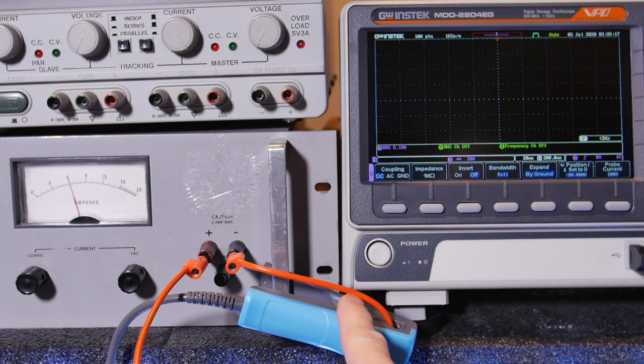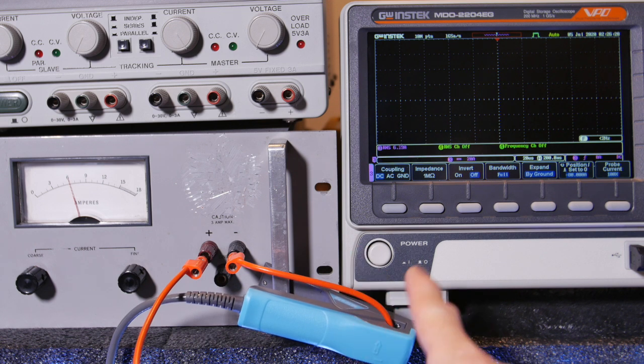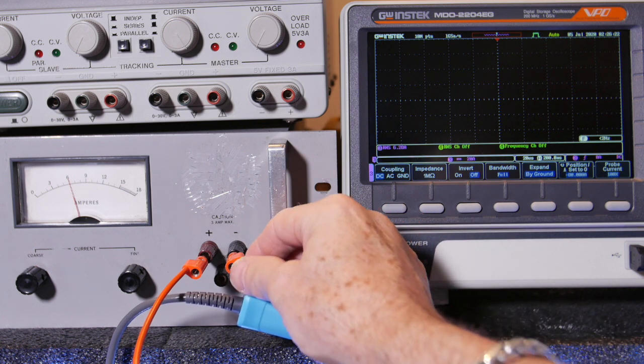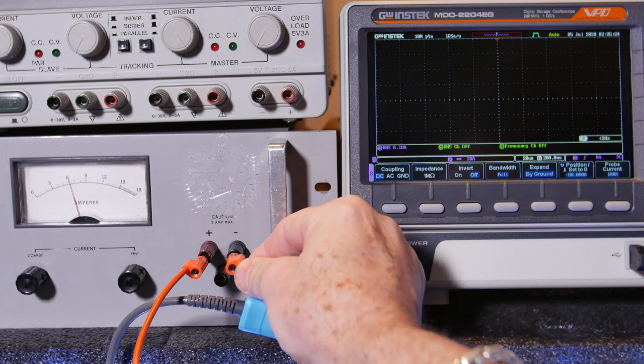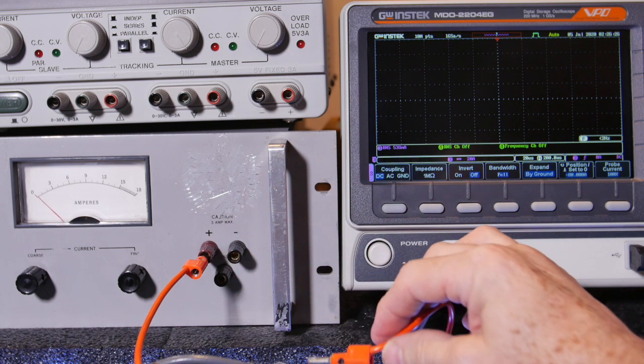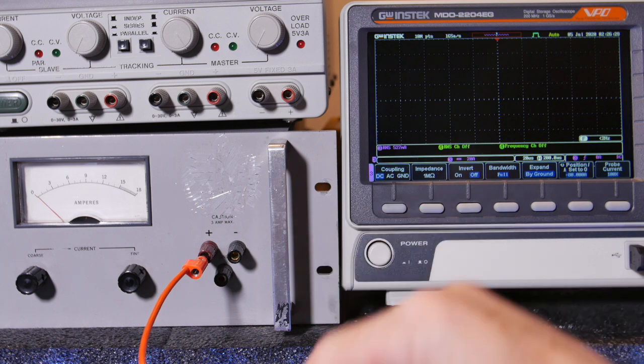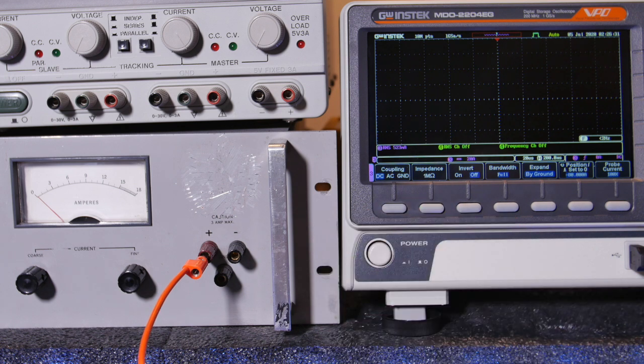Let's try zeroing the probe to see if we get a better reading now that we've got it in the 100 amp setting. Pull that out. You can't have any current going in there when you're trying to degauss, right? So hit, now listen for it.